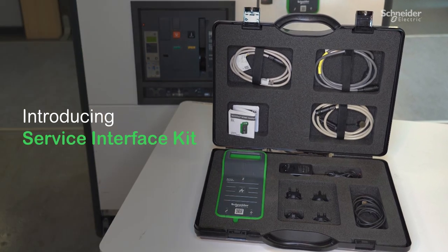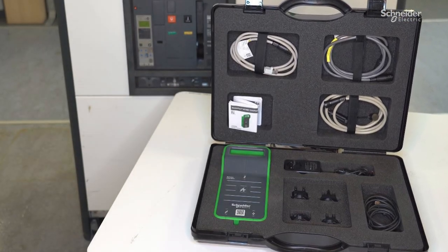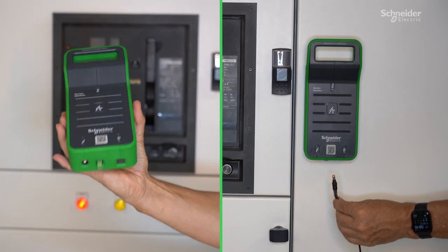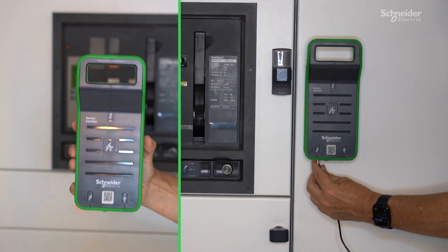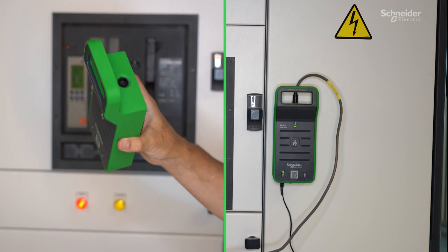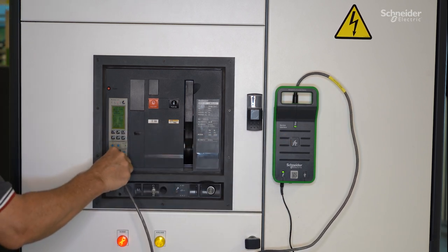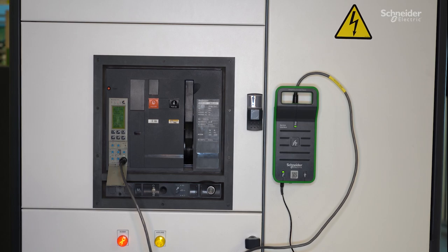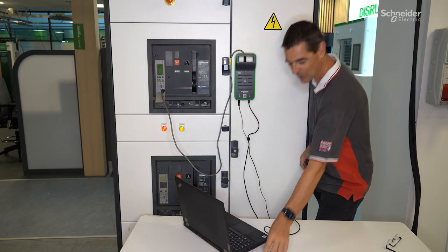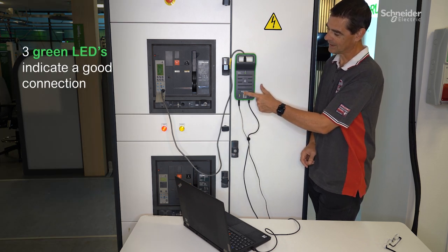To connect to MasterPact MTZ, NW, and Compact NSX, you will need a service interface kit. In order to establish a connection, you have three steps. Step one: connect the service interface to the power supply. Step two: use the right cable to connect the service interface to the circuit breaker. Step three: use the USB cable to connect the service interface to the laptop. Ensure all three LEDs are green.